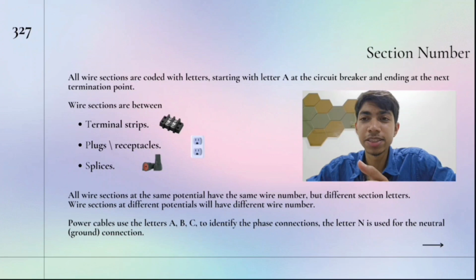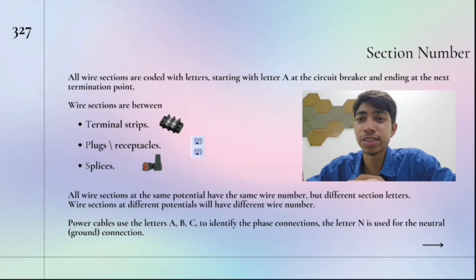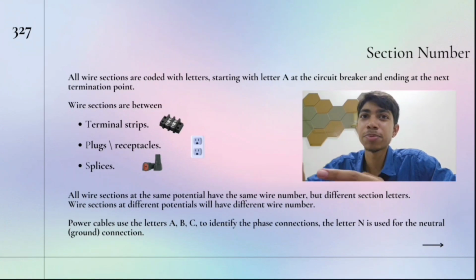Power cable identification. For power cable identification, specific letters are used to identify phase connections. These are typically A, B and C. The letter N is used to denote the neutral or ground connection, which is a reference point in an electrical circuit from which voltages are measured, a direct physical connection to the earth or a connection to some conducting body that serves in place of the earth.